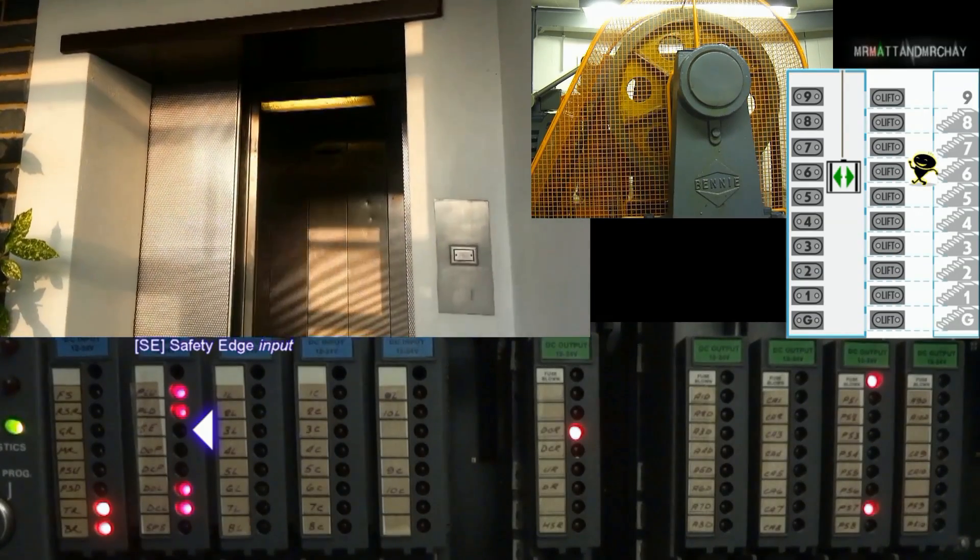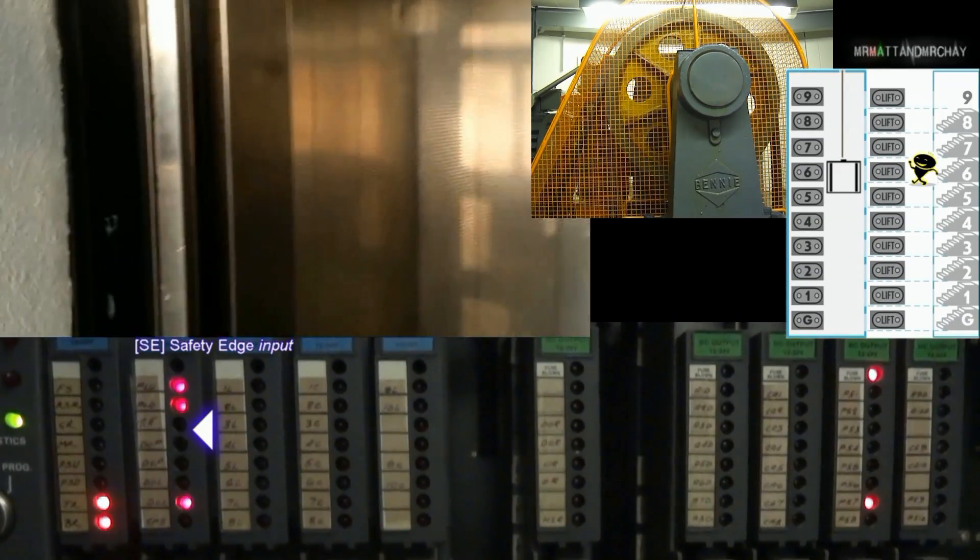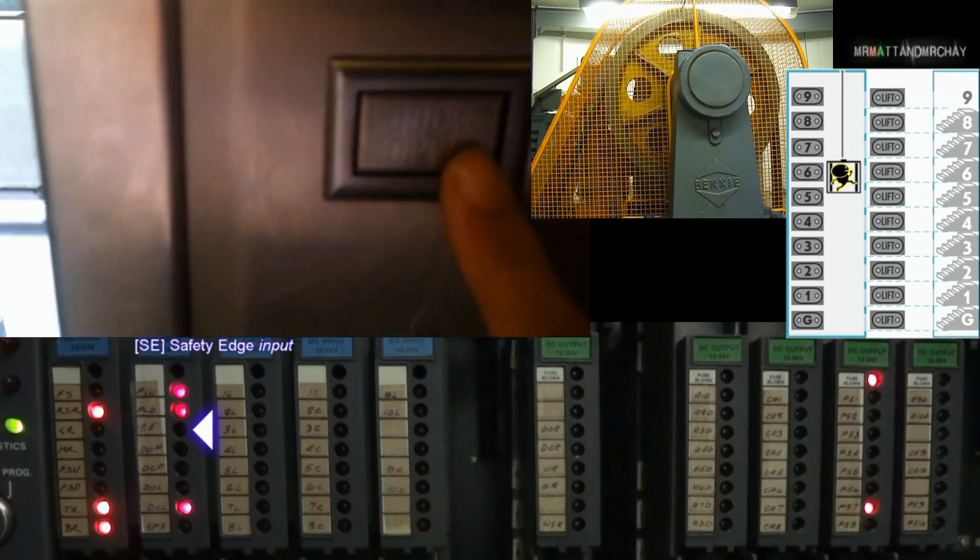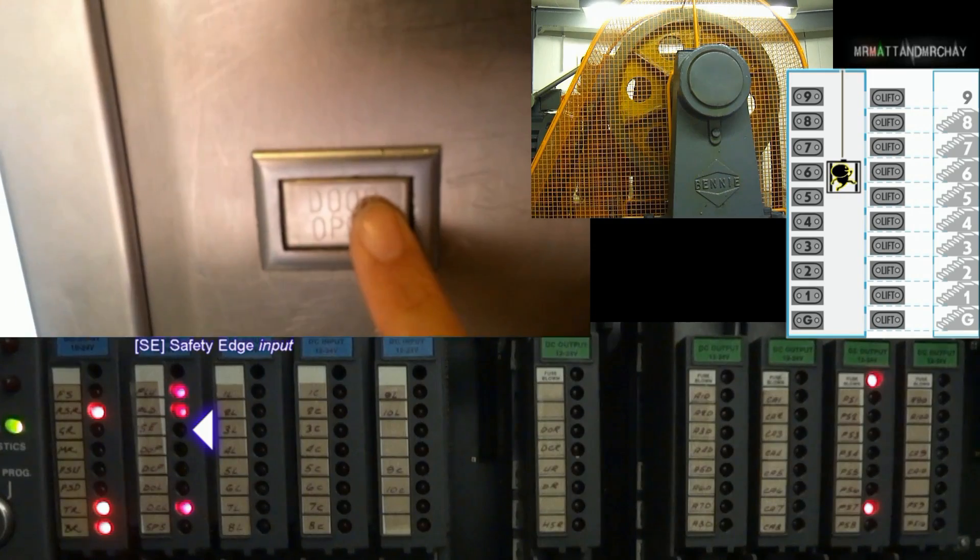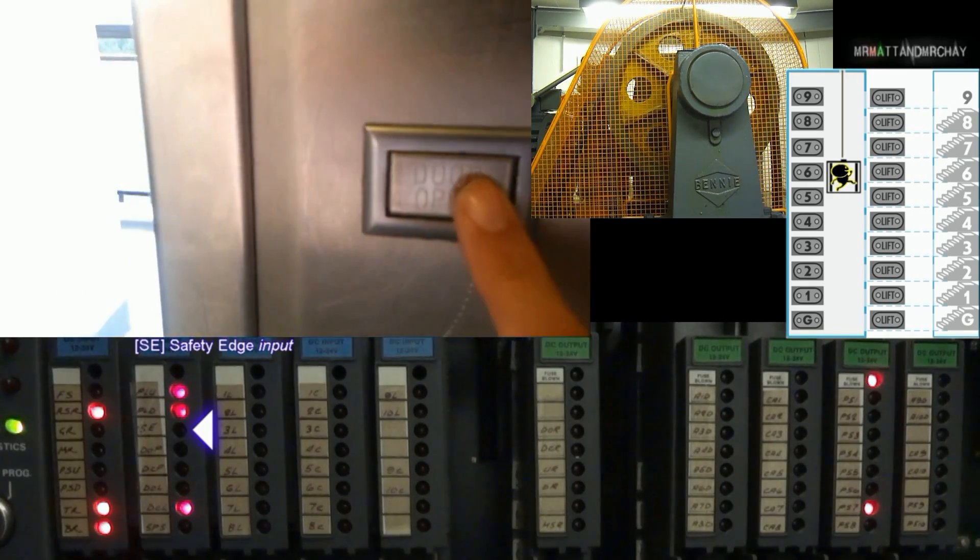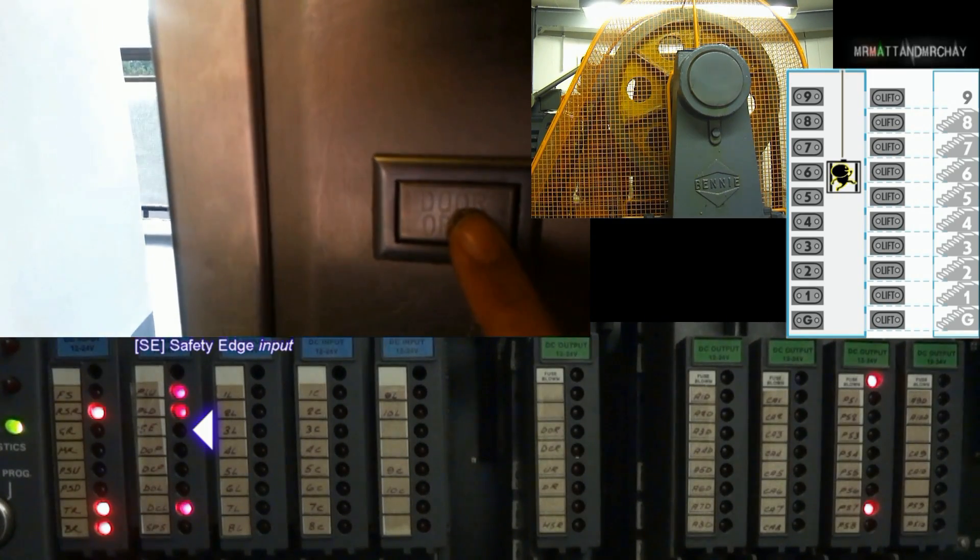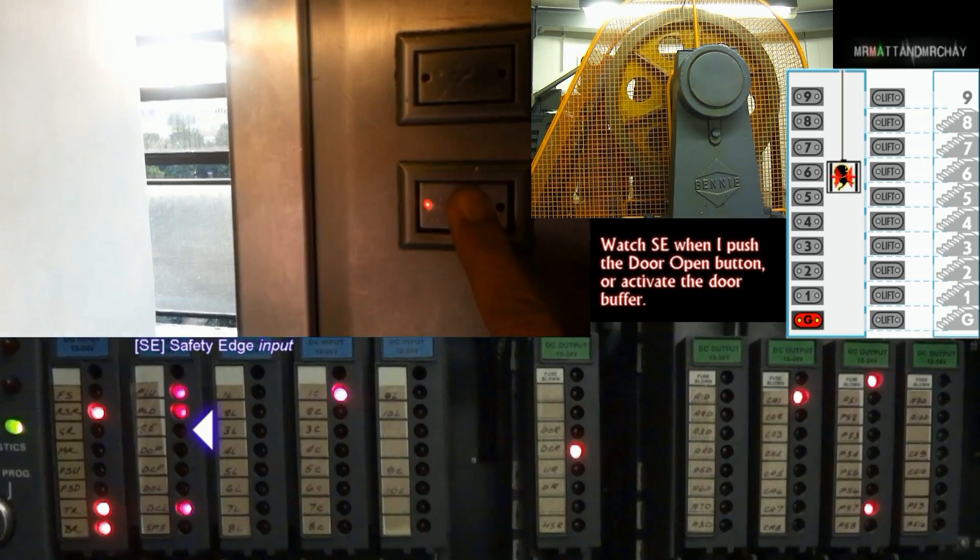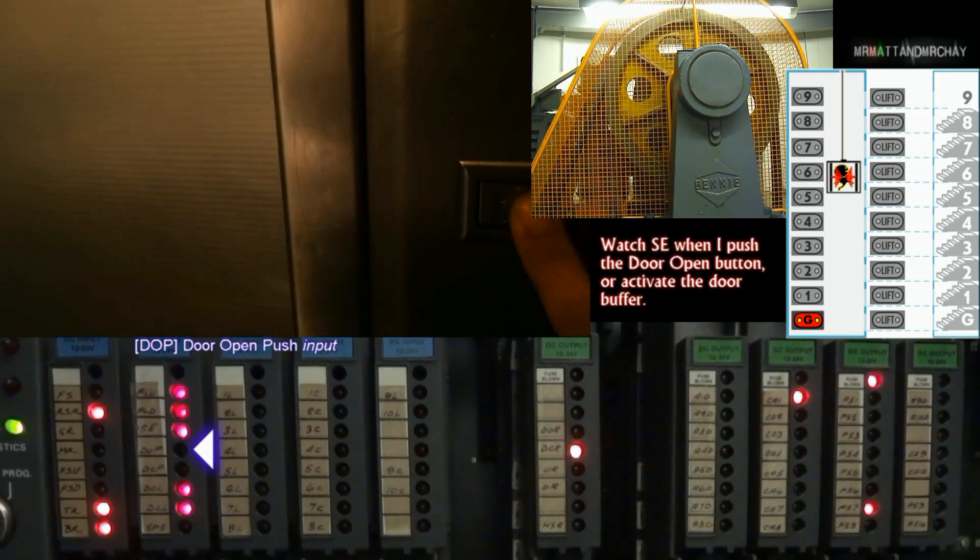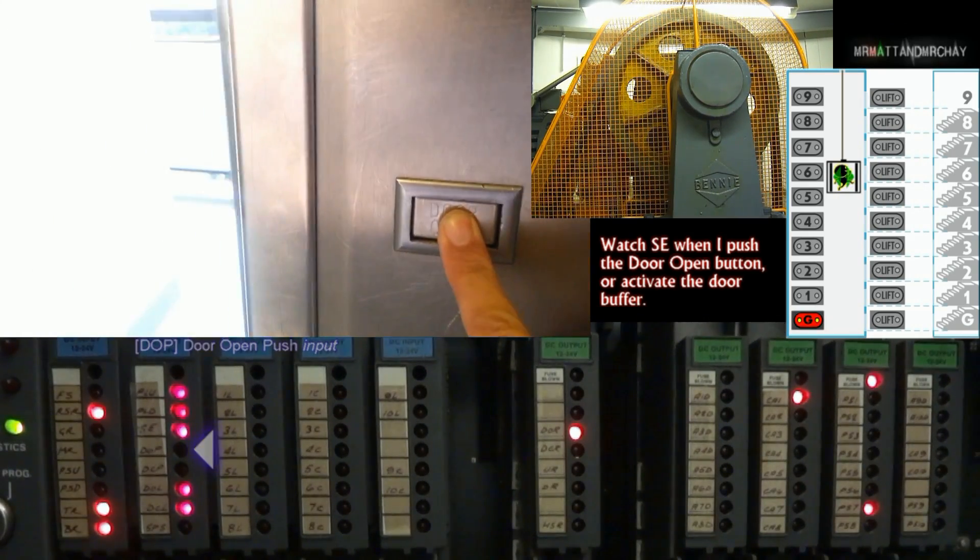SE, safety edge. This is usually a beam across the door, which reopens when someone gets in the way. But in this installation, it's an old style door buffer. For some reason, the door open button has also been wired into here, instead of its dedicated DOP input, which for some reason is not used.